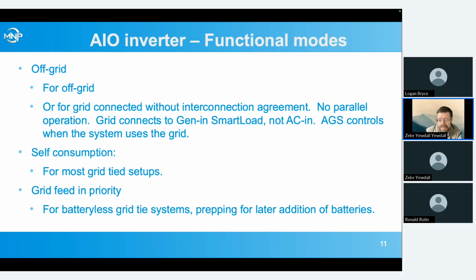Even in zero export, if you don't have all the settings right, specifically always drawing a little bit from the grid to take into account the little blips when load changes, it might take a second or two for the inverter to respond to that change in the load, and you might sell power to the grid for a second or two. The more advanced utility meters can tell that, and you will get in trouble with the utility. By operating in off-grid mode with the grid just basically pretending to be a generator, it works a little more safe doing that. Legally, if you're going to operate in parallel with the grid, you need an interconnection agreement, even if you're not selling to the grid.